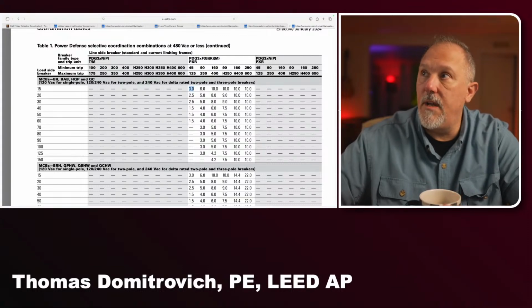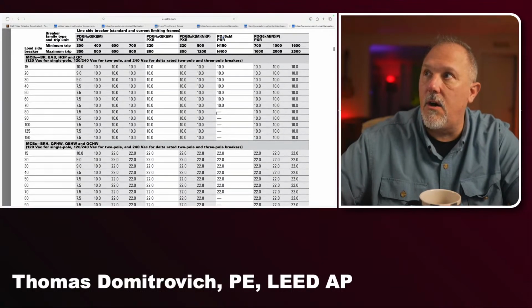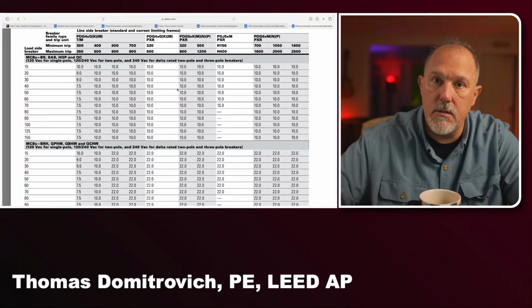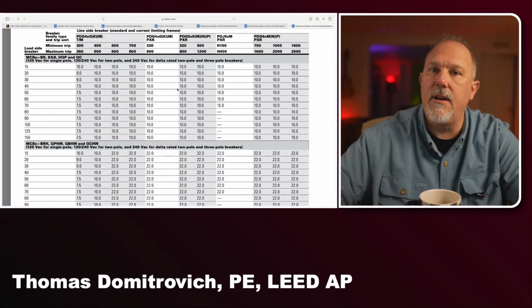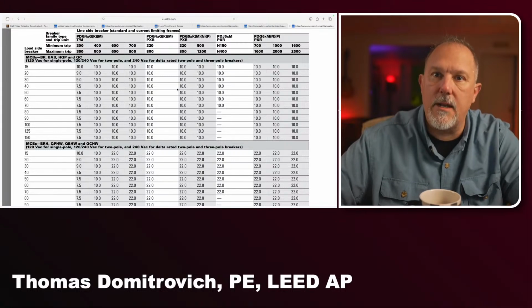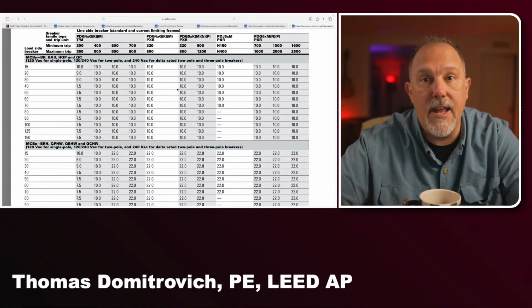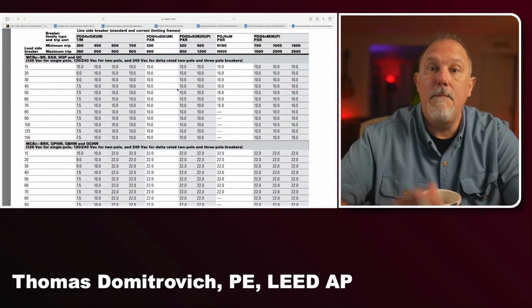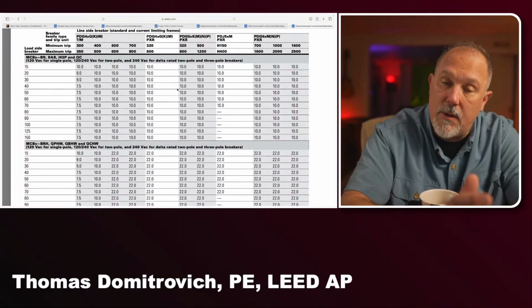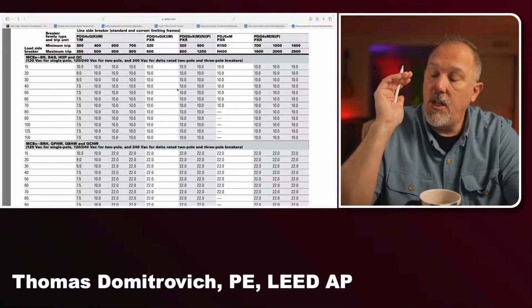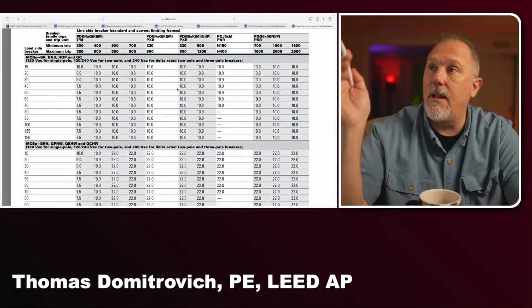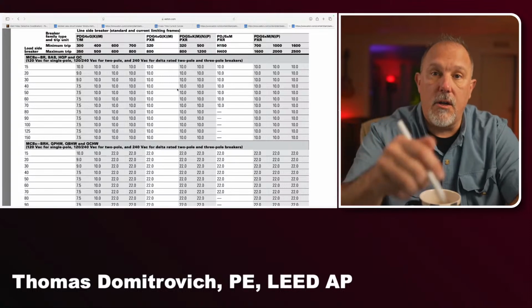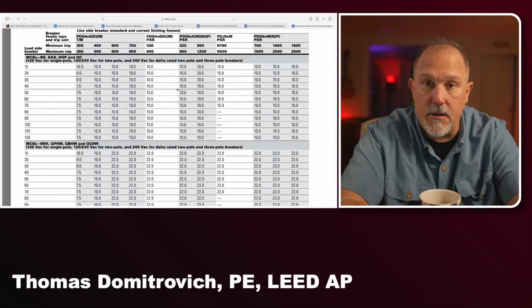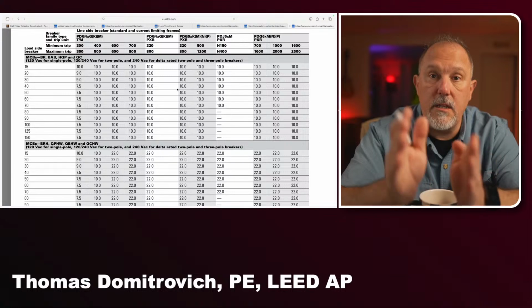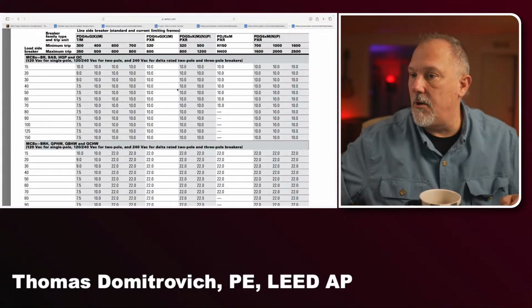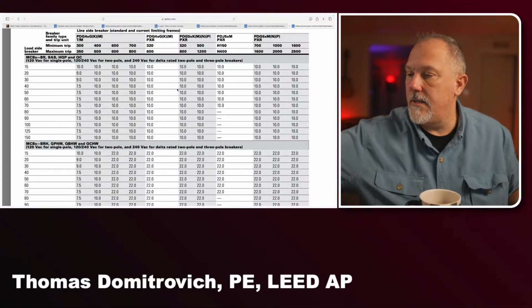Okay? So many of these breakers that you're looking at all have adjustable trip units. They all have short time delays. They'll have long time delays. They'll have short time pickups and all that jazz. They might even have an adjustable instantaneous. And we ship everything at the lowest set points. So if you install it and think, well, I did the tables, I installed it, I accepted factory defaults, it ain't going to work. You need the set points. All right?